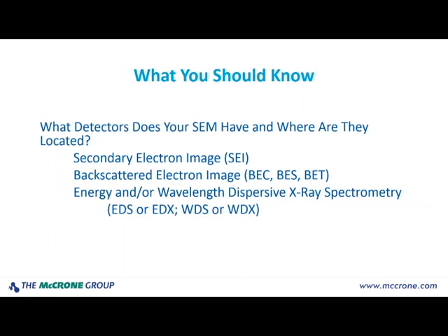So other things you should know: you want to find out what detectors are on your SEM and where they are located. Where they're located is going to play a big factor in interpreting your data. Do you have a secondary electron detector? And if so, how many? Where are they? Do you have backscattered electron imaging capability? Typically this is going to be at what's called a composition mode, designated maybe as BEC. But if you have another detector right adjacent to it, you can add a condition called shadowing — that's a BES designation — and it adds quite a few useful features to the image. There is also BET, which is looking at topography. These detectors interact with one another; signals are added and subtracted to get the image, but it gets you a lot of useful information.